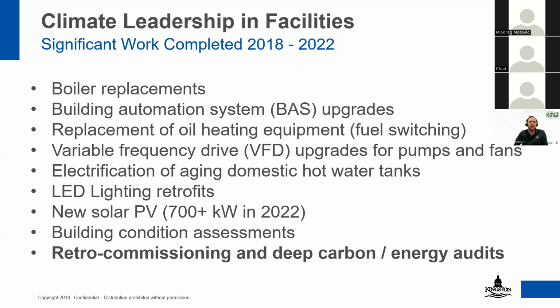We're continuing to update our building automation systems and actually integrate artificial intelligence into those BAS systems. As Dan mentioned, we're not just using it to create a setback for temperature. We're using it to optimize the facility and identify small issues a human eye may not notice, but over time an analytical code can delineate that there's a heating valve leaking or something overcooling. All of that is being integrated directly into our building automation system, so it's a true brain of the building that understands what's going on.